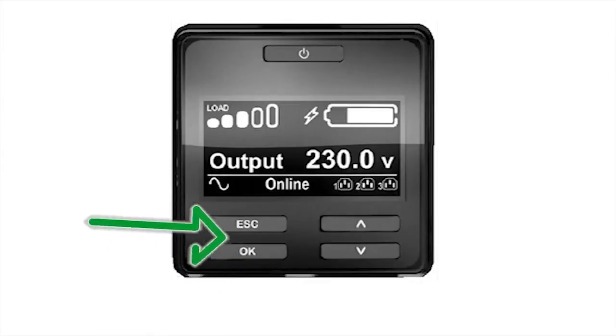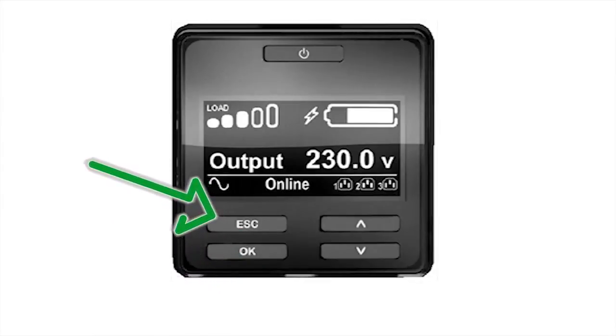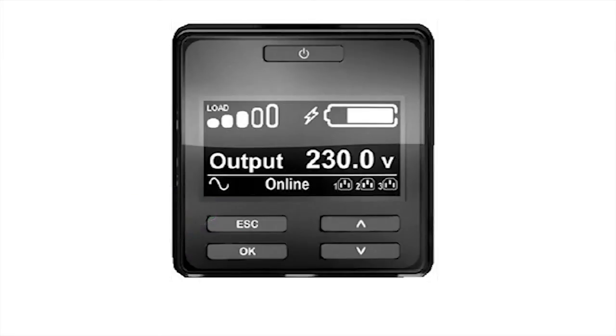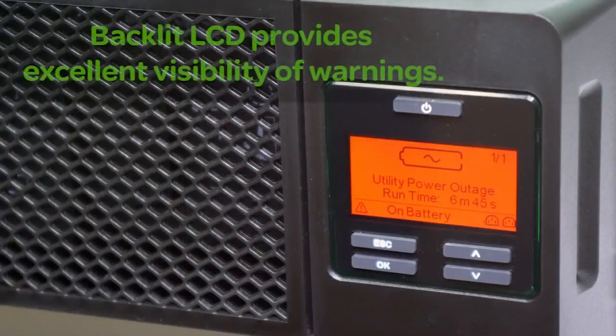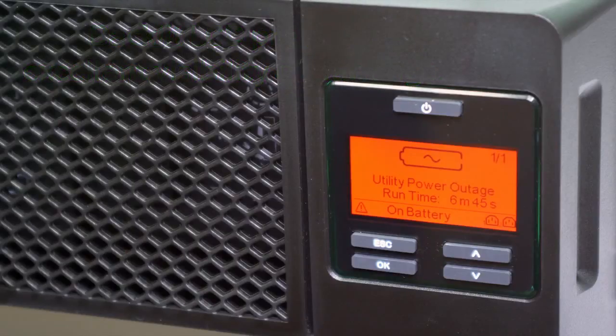Pushing the Escape button will return you to the previous screen. All configurable UPS settings can be provisioned through the LCD. The display also informs you of potential issues. There are two types of warnings. Screens that are backlit in orange warn of conditions where the UPS is operating outside of its intended configuration.